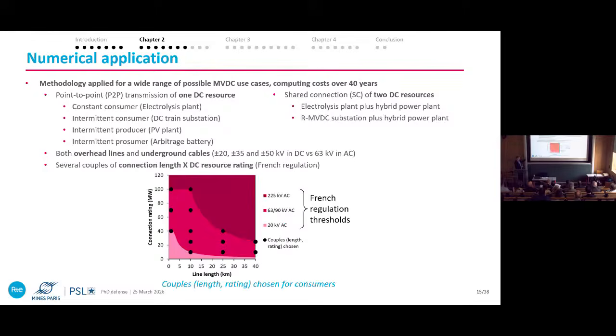I tested several couples of connection length times DC resource rating, since it depends whether you want to connect 10 kilometers, 10 megawatts, etc. In France there is regulation, and the connection to 63 kilovolts depends on line length and connection rating. So I explored the black dots here, respecting the French regulation thresholds, which is why I explore low rating with high length, and high rating with low length.